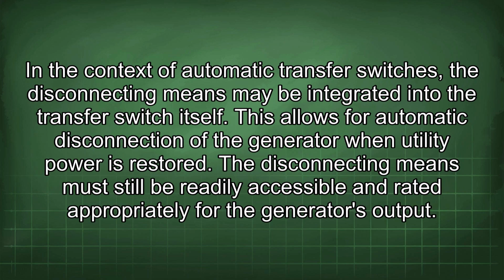In the context of automatic transfer switches, the disconnecting means may be integrated into the transfer switch itself. This allows for automatic disconnection of the generator when utility power is restored. The disconnecting means must still be readily accessible and rated appropriately for the generator's output.